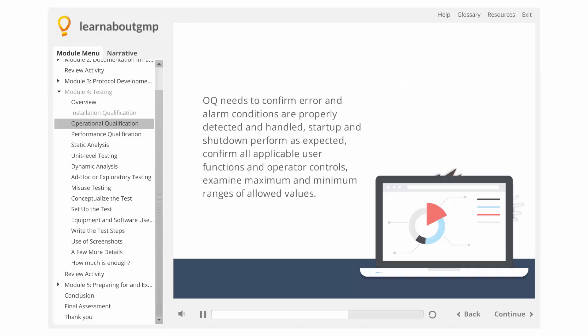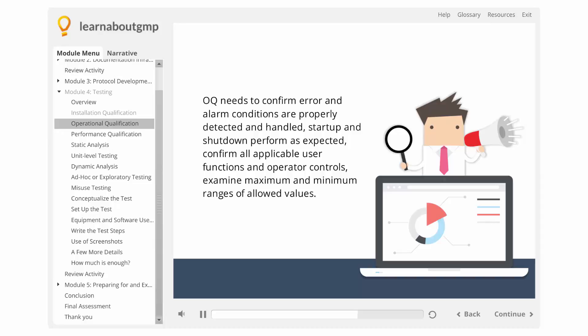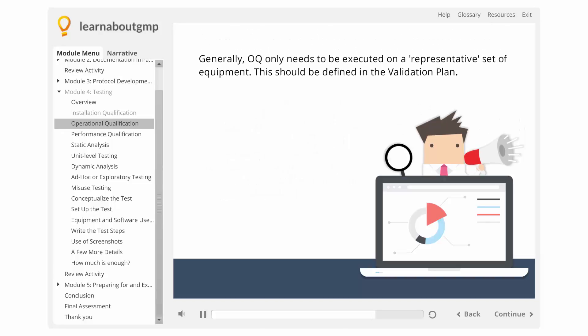OQ needs to confirm error and alarm conditions are properly detected and handled, startup and shutdown perform as expected, confirm all applicable user functions and operator controls, and examine maximum and minimum ranges of allowed values.